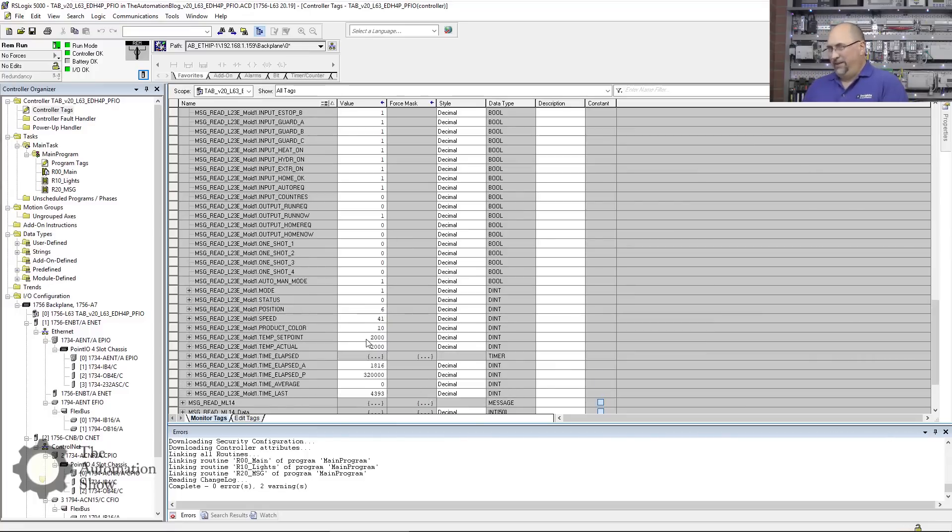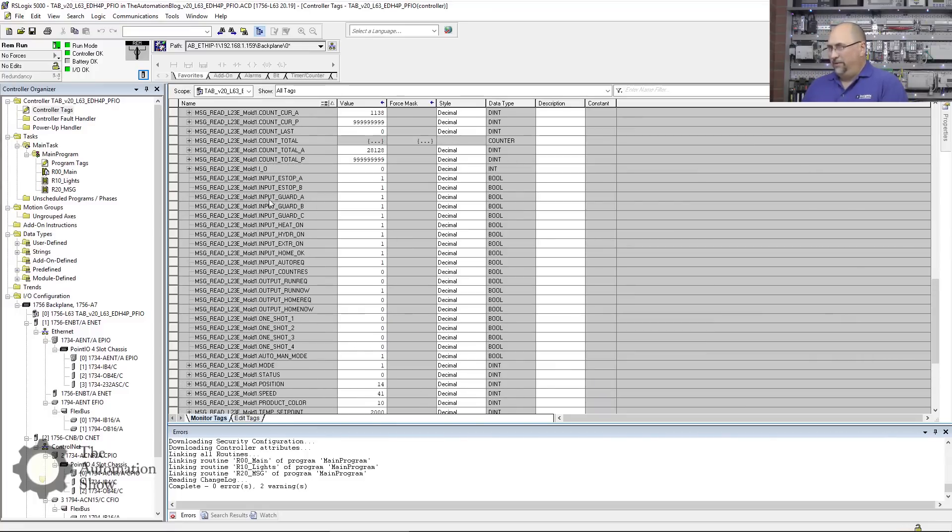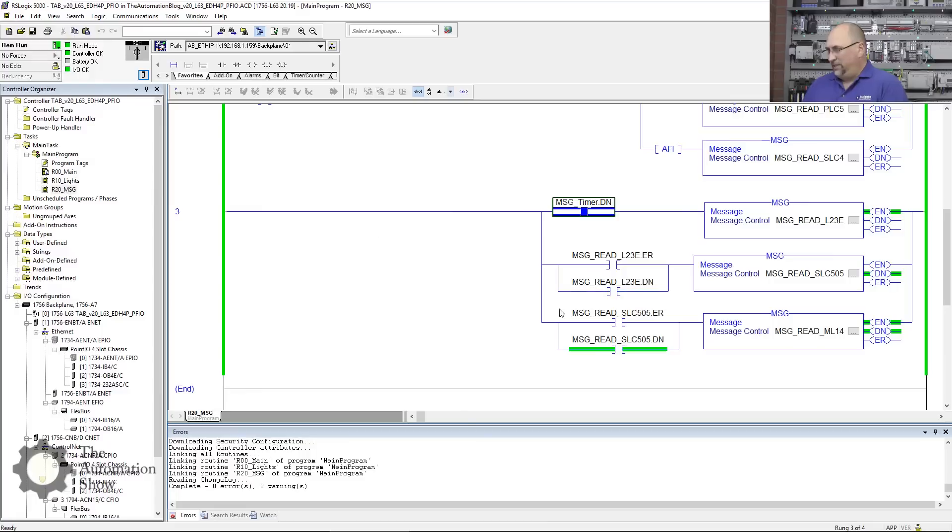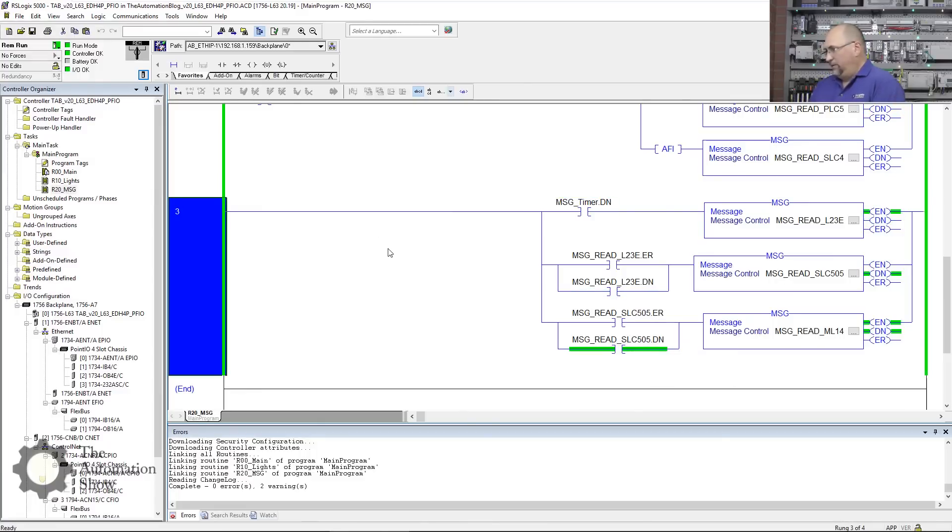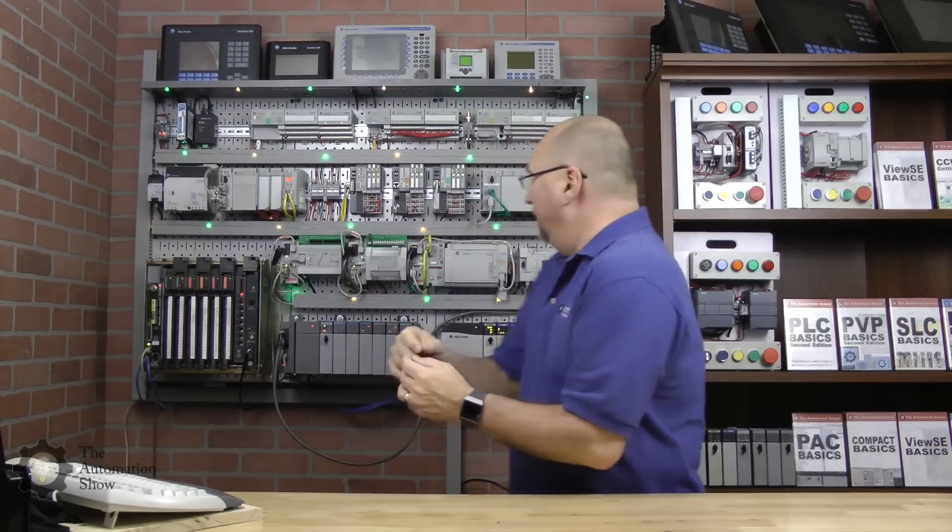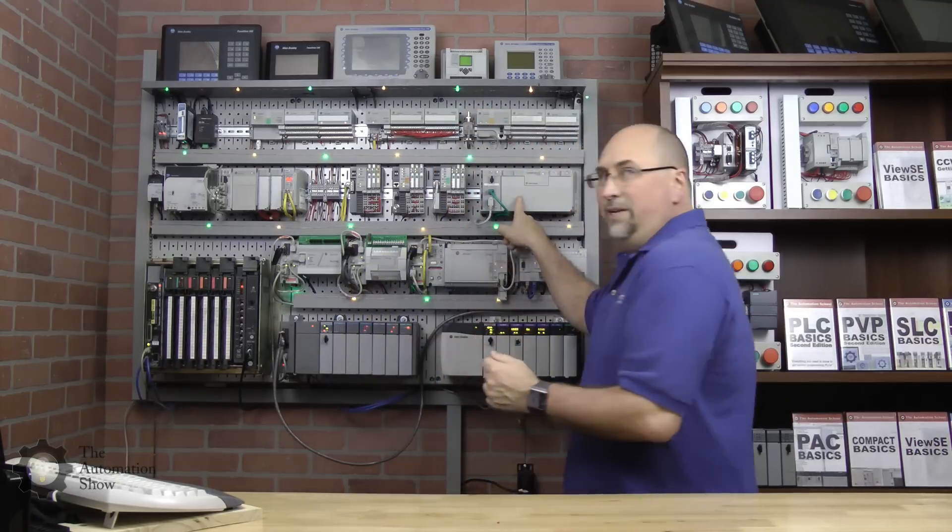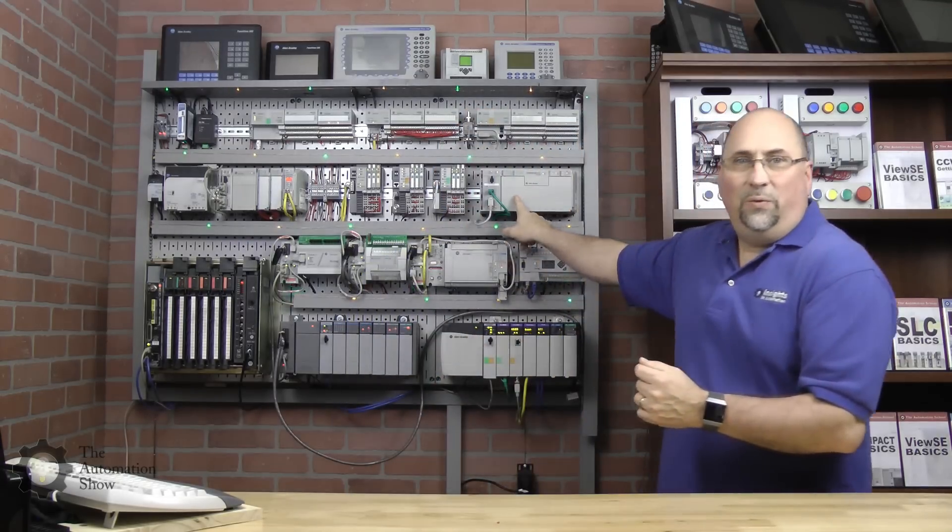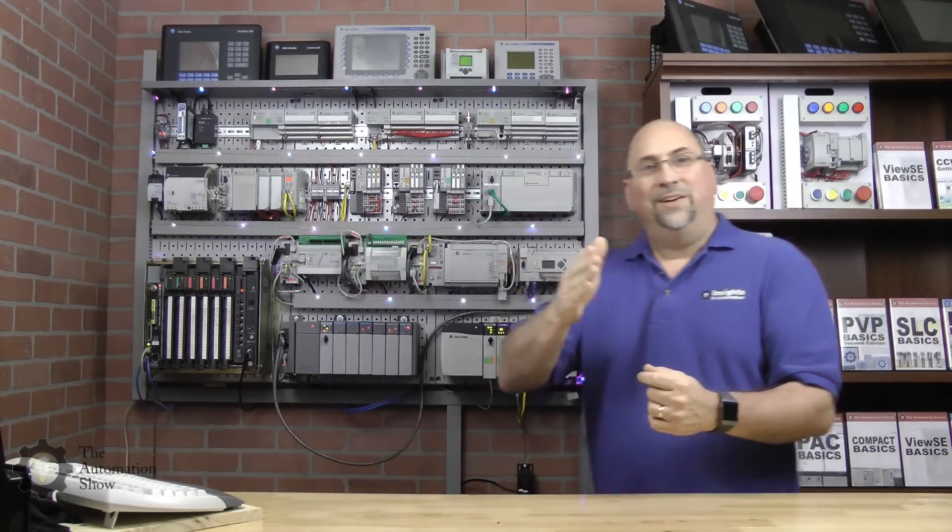All right, so with that, we have successfully read data into our Control Logix from a Compact Logix—especially with that weird path we have to kind of go to the backplane and the Ethernet card even though everything's all in one. We still have to kind of build that path. And then we went to the SLC 500 and the Micro Logix—those were easy. There was no path, you put the IP address in as the last item and that was it. And now we're reading that data in with all the other data.